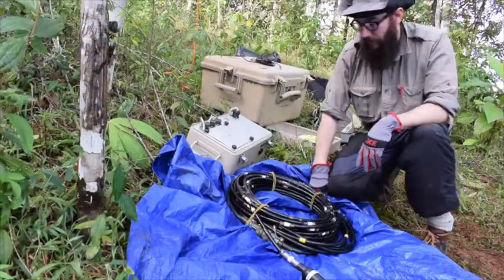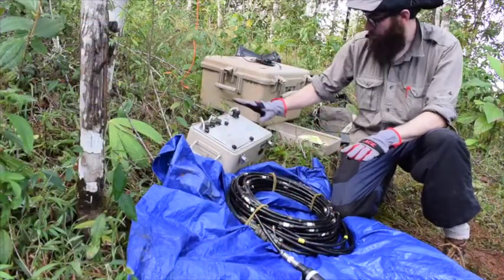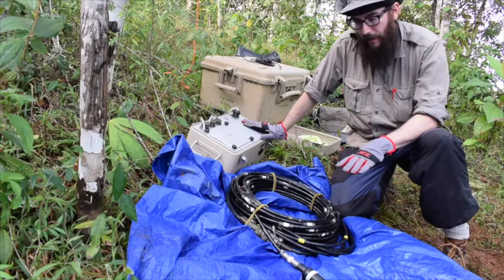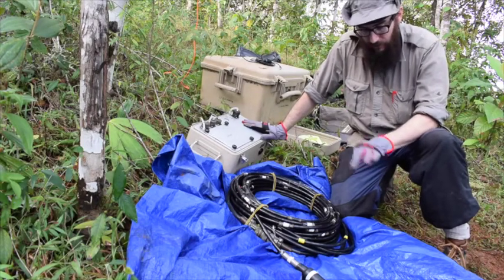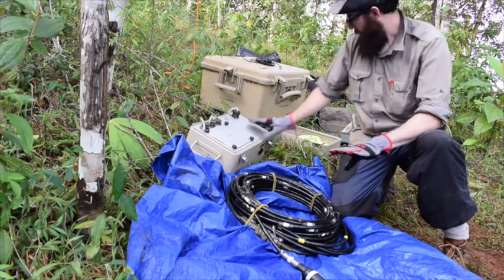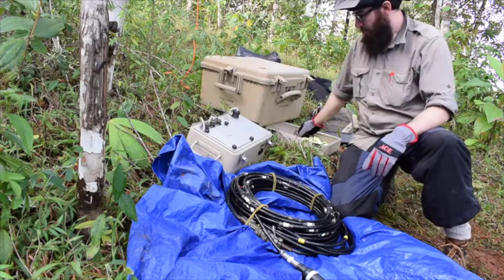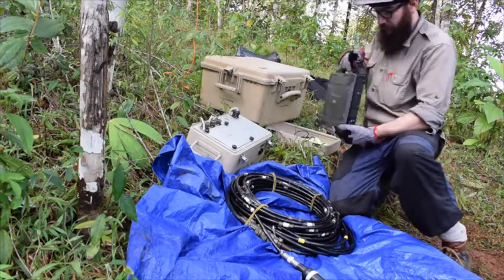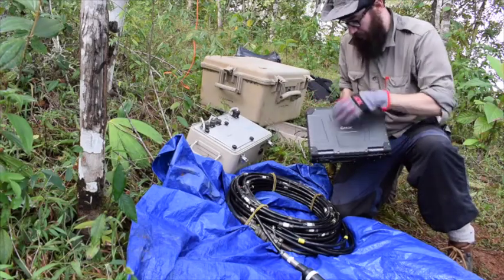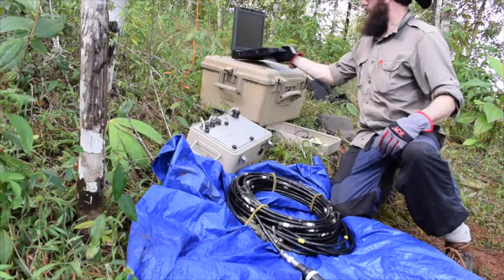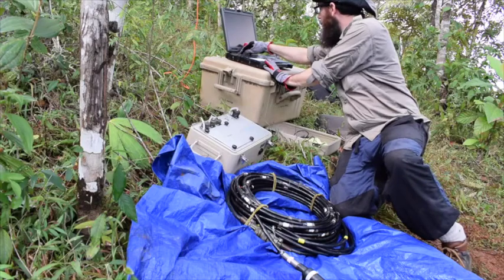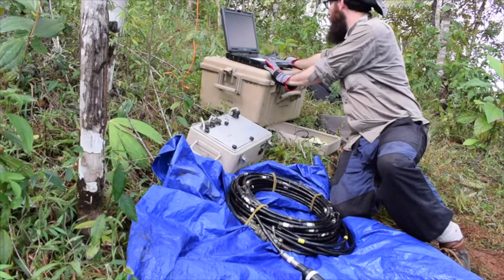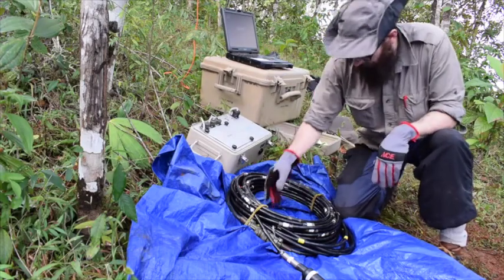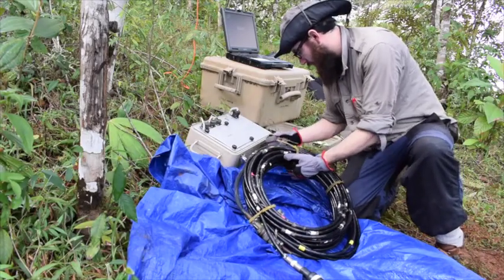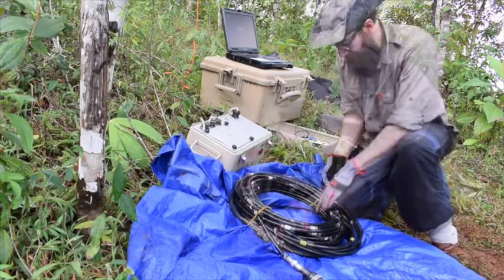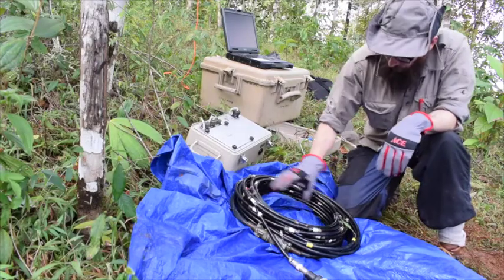The next thing we're going to do is connect the probe to the dart and just do a test measurement to make sure that everything is working properly. So often the best thing to do is start turning on the computer now. Takes a minute to boot up. And then just take these cable ties off.